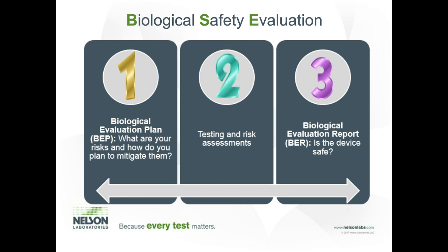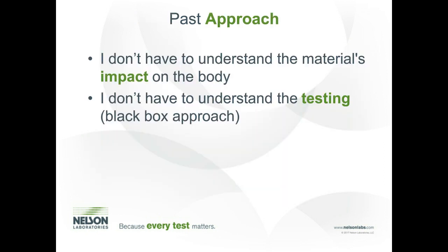And I've used this example before, so if you've heard one of my webinars or seminars, I apologize, but I really think it's the best way to explain what we're looking for. We're still seeing the checkbox mentality that has been in the industry for the last 5 or 6 years, where people would just look at the ISO 10993 table, determine what the contact of the medical device is, and then just do what testing is required for that medical device, just checkbox. And that just doesn't work anymore.